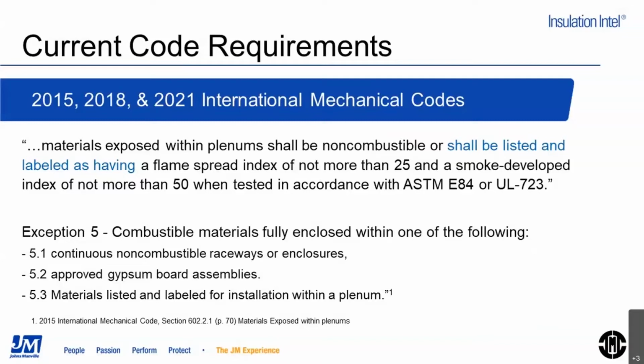There is, however, Exception 5, which says that combustible materials fully enclosed within one of the following can also be used. And what are those exceptions? We have the first one, which is continuous non-combustible raceways or enclosures, approved gypsum board assemblies, or materials listed and labeled for installation within a plenum. So there's a few ways combustible materials can also be used within the plenum. And again, why are we concerned about all of this? If you remember earlier in the definition for the plenum, the air is allowed to move between the plenum space and the occupiable space. Because of that, we really want to be very careful of what is allowed in that space to not have a fire hazard.